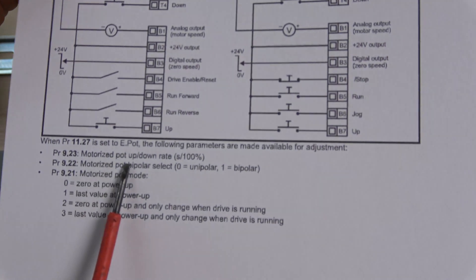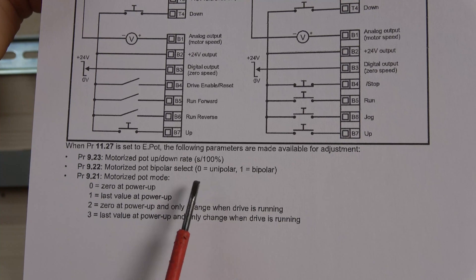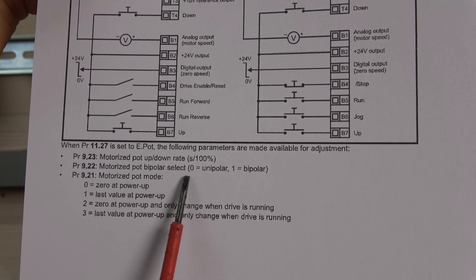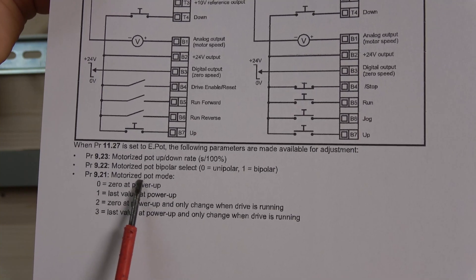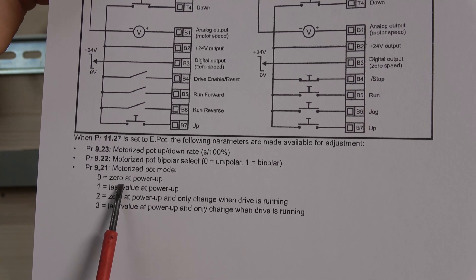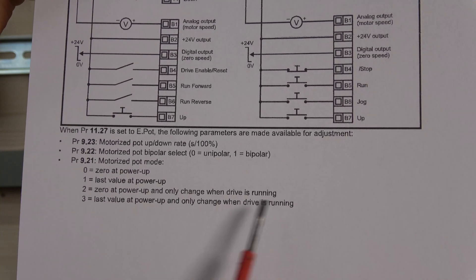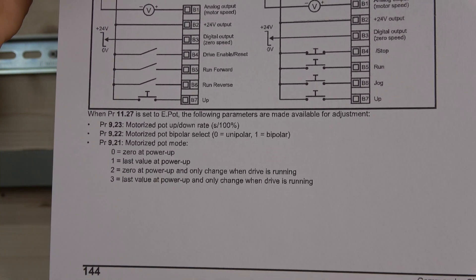In parameters 9.23, 9.22, and 9.21, that pretty much explains your motorized pot up/down rate, which is how sensitive the button is going to be, motorized pot bipolar selection, and motorized pot mode. You can have zero power up, last value at power, and how it saves your values as your speed goes up and down.